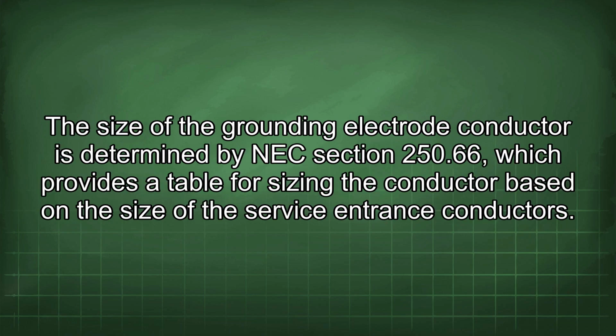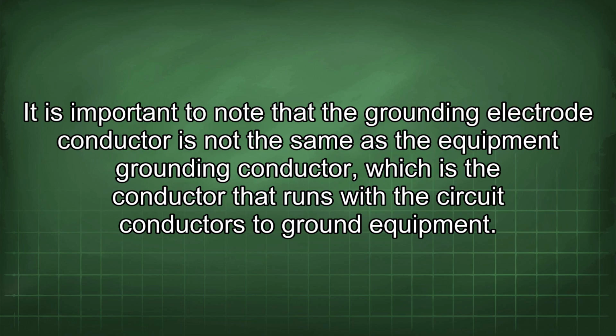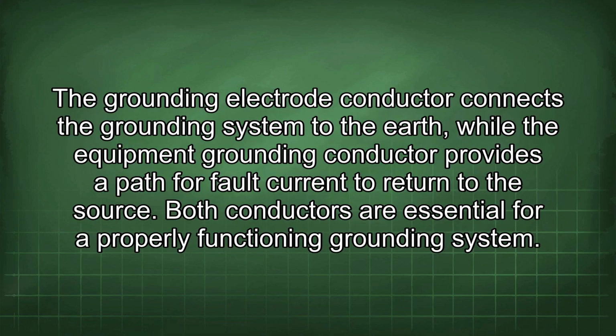The size of the grounding electrode conductor is determined by NEC section 250.66, which provides a table for sizing the conductor based on the size of the service entrance conductors. It is important to note that the grounding electrode conductor is not the same as the equipment grounding conductor, which is the conductor that runs with the circuit conductors to ground equipment. The grounding electrode conductor connects the grounding system to the earth, while the equipment grounding conductor provides a path for fault current to return to the source. Both conductors are essential for a properly functioning grounding system.